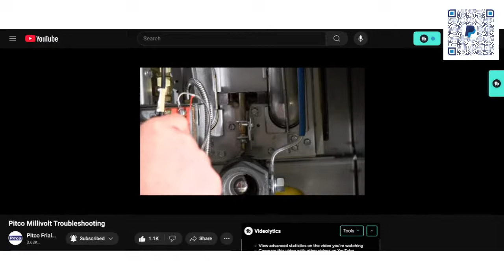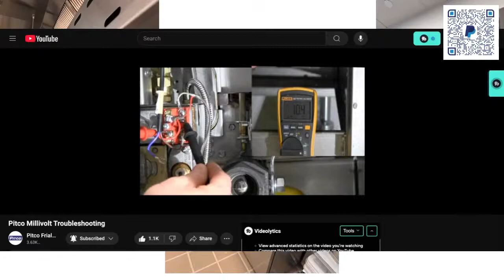With the blue wire removed, apply your meter to terminals TH2 and PP1 in order to check the resistance of the pilot valve. Now this applies to Fry Master. The proper reading should be approximately 10.5 ohms.